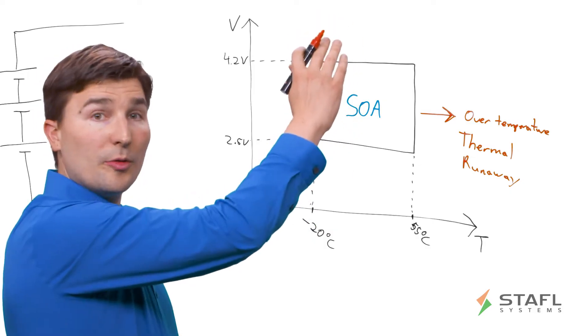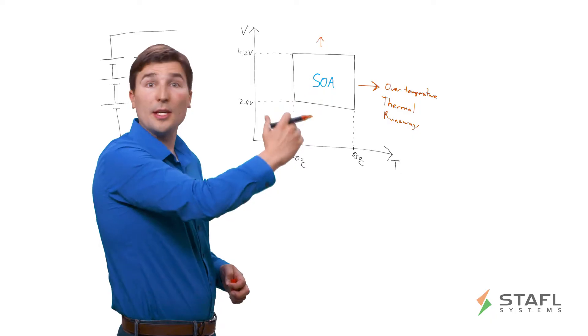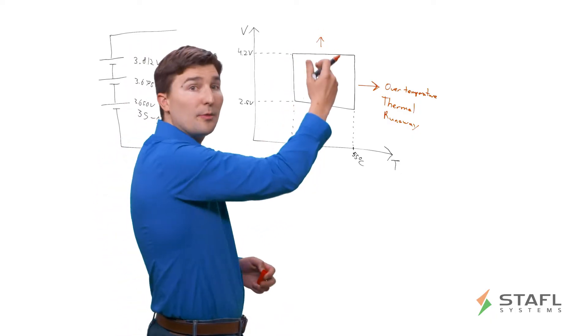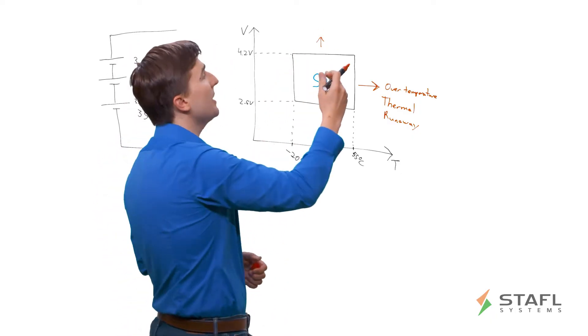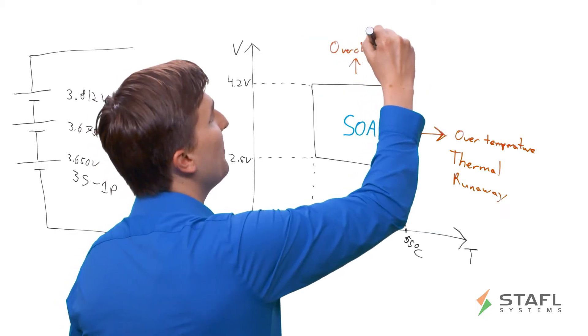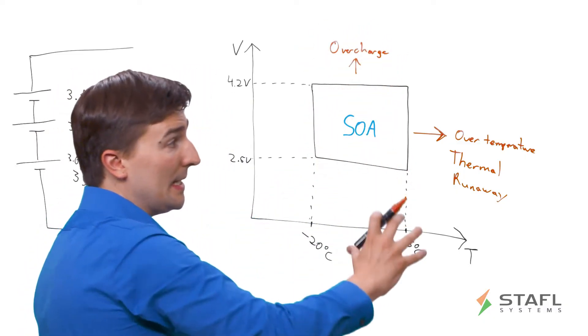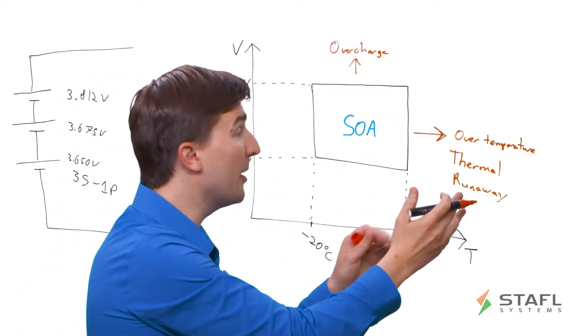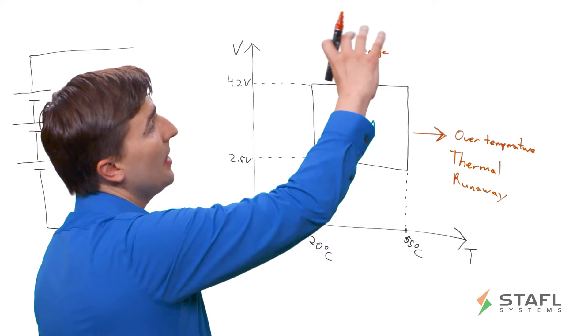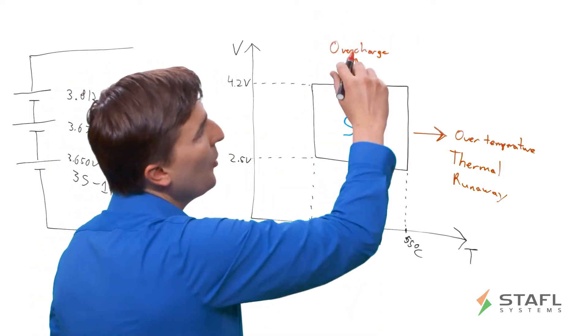So that's the over-temperature side. What about on the over-charged side? So this is if you have a lithium-ion cell that goes above, say, 4.2 volts per cell. If you start climbing to 4.4, 4.5, 4.6, what you do is you enter into what's called the over-charge regime. And what this can trigger is, in effect, it can actually trigger a thermal runaway because the cell no longer can safely hold that charge.